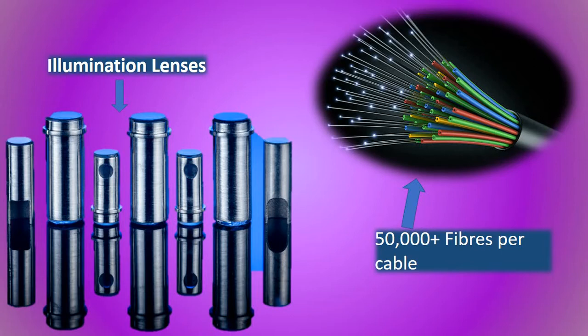The fibre optics of the endoscope make up one of the most complex pieces of technology in the tool. The endoscope typically contains 2 or 3 illumination lenses, each of which are made up of about 50,000 separate optical fibres. 1 or 2 of these cables carry light into the body, and another carries reflective light back into the physician's eyepiece or the camera.